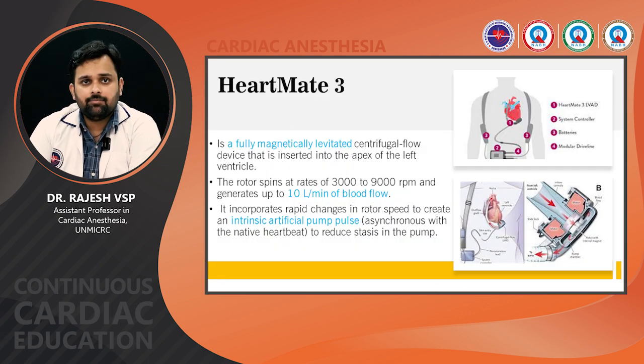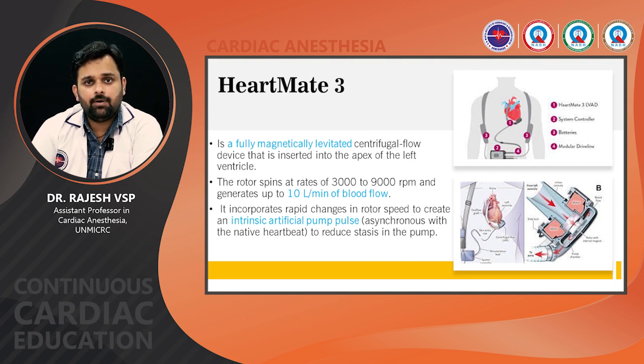Next in this is HeartMate 3. This is also a fully magnetically levitated centrifugal flow device that is inserted into the apex of the LV. It spins at 3000 to 9000 RPM and generates up to 10 liters per minute of blood flow. It incorporates rapid changes in rotor speed to create an intrinsic artificial pulse, asynchronous with the native heartbeat, to reduce the stasis in the pump.